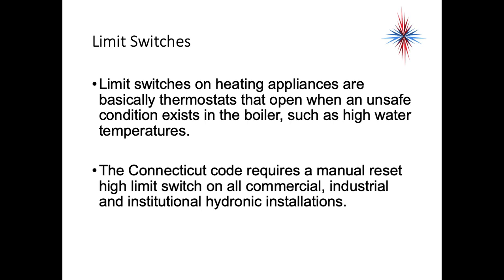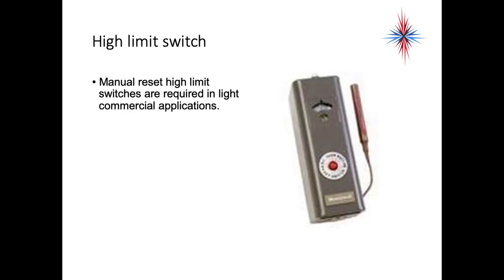In Connecticut, the code requires a manual reset high limit switch on all commercial, industrial, and institutional hydronic installations. The Connecticut code is actually duplicated in many other states because it is international building code. So always check the code for your area and make sure you have the appropriate safeties.